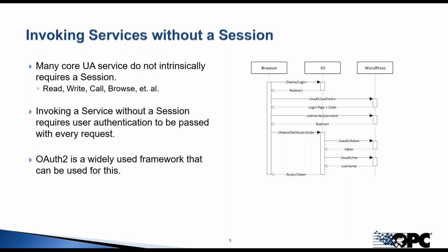However, a lot of the OPC UA services don't really require a session, which is why we introduced this concept into part 1.04 called sessionless service invocation, where basically we say, well, okay, if you're not subscribing, you just want to read a value, you don't need a session. So here's how you do that. We spec'd all that out. And this gives you the possibility of doing simple REST-like calls to a UA server and getting back results.